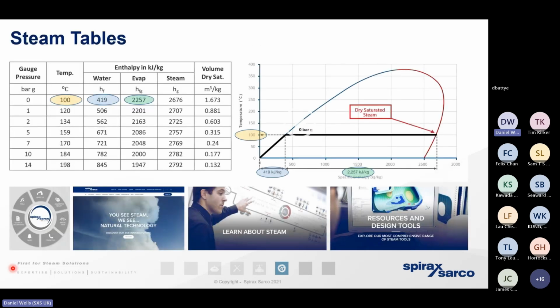One of the first things really to cover off is that dreaded slide that I keep harping back to: the steam tables. They bring together all of those relationships. The pressure temperature relationship, the pressure volume relationship, the energy that the water needs to contain before it's going to boil off and generate steam, the energy we need to add to the boiling water in order for that to happen, and the total heat energy of the steam. So the steam tables really demonstrate how all of those relationships and values change as we manipulate the pressure, whether that's the pressure of the steam in the boiler, in the pipework, or at the heat exchanger itself.